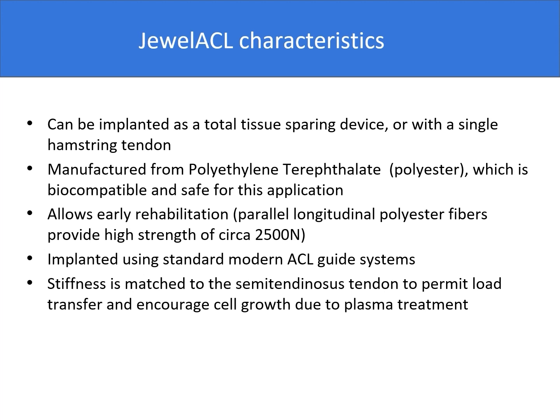The JewelACL can be implanted as a total tissue-sparing device or with a single hamstring tendon. It is manufactured from polyethylene terephthalate, better known as polyester, which is biocompatible and safe for its application. It allows early rehabilitation as its longitudinal polyester fibers provide strength of nearly 2500 newtons, can be implanted using standard modern ACL guide systems, and its stiffness is matched to that of the semitendinosus tendon to permit load transfer and encourage cell growth due to plasma treatment.